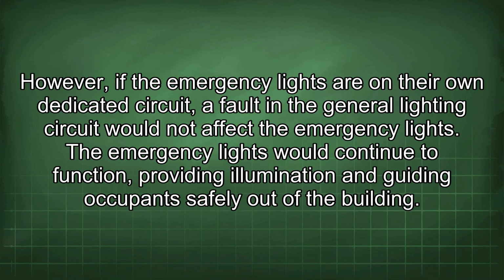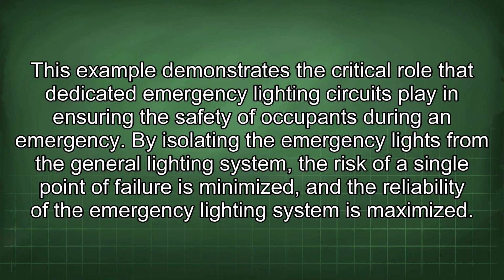However, if the emergency lights are on their own dedicated circuit, a fault in the general lighting circuit would not affect the emergency lights. The emergency lights would continue to function, providing illumination and guiding occupants safely out of the building. This example demonstrates the critical role that dedicated emergency lighting circuits play in ensuring the safety of occupants during an emergency. By isolating the emergency lights from the general lighting system, the risk of a single point of failure is minimized and the reliability of the emergency lighting system is maximized.